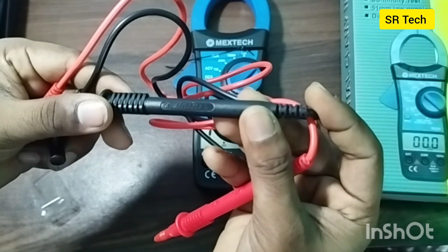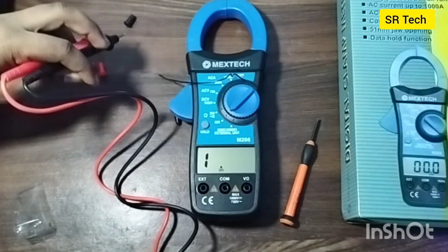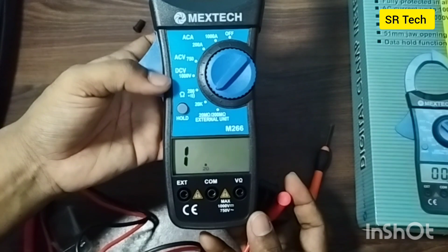I will remove the caps from this test lead, and we'll see how to connect the test lead in the terminals to check all the features like voltage, resistance, and continuity. I have removed all the caps from the probe, and here there are 3 jacks: EXT, COM meaning common, and the last one is V for voltage.